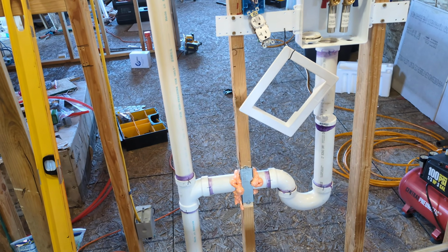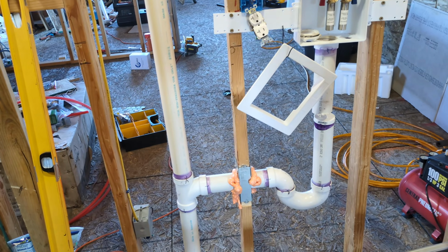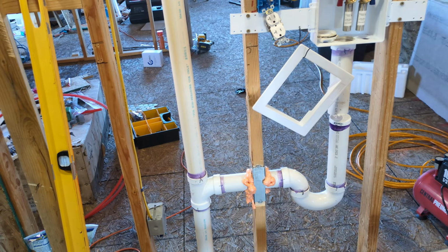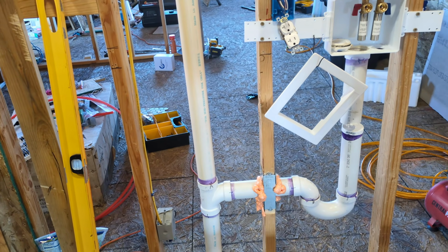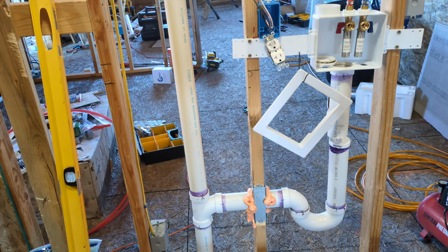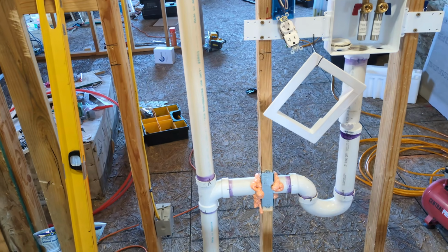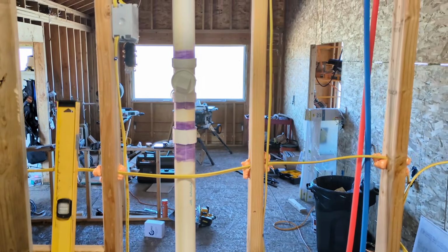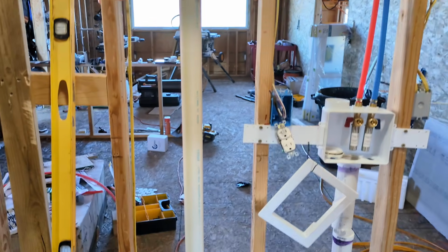The second guy, who has spent more time actually doing plumbing than inspecting, he's newer on the inspecting side, I think, said that's a terrible idea. He's done a ton of plumbing, and he's like, when you run that thing down there, it's going to smack you in the face. Especially if it's motorized, there's just no way to really snake it comfortably, and it's going to be a real pain for service. But it is legal, so he's allowing it, especially since the first inspector recommended it. But in any case, you need a clean out on your 2-inch line for your washer.